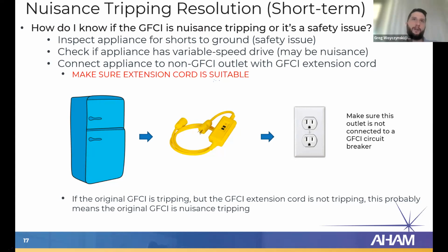Let's use the example of a refrigerator. Let's say the refrigerator is plugged into a receptacle that is protected by a GFCI breaker. And that GFCI breaker keeps nuisance tripping. And you've done your inspection on the refrigerator. Everything is fine. It's operating safely. You can unplug that refrigerator, plug in a GFCI extension cord and plug it into a receptacle in a hallway. And you want to check the breaker box just to make sure that that hallway receptacle isn't also connected to a GFCI. A lot of times it's not.